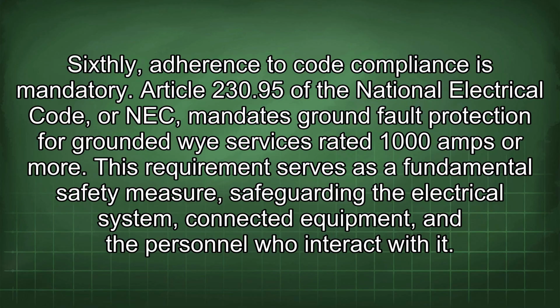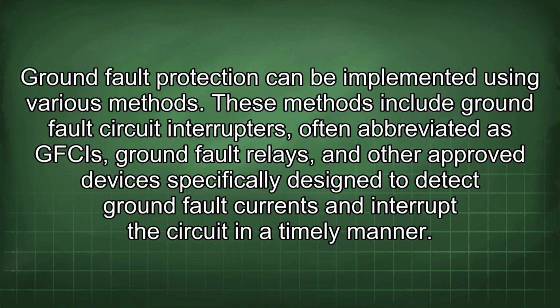Article 230.95 of the National Electrical Code, or NEC, mandates ground fault protection for grounded Wye services rated 1000 amps or more. This requirement serves as a fundamental safety measure, safeguarding the electrical system, connected equipment, and the personnel who interact with it. Ground fault protection can be implemented using various methods.